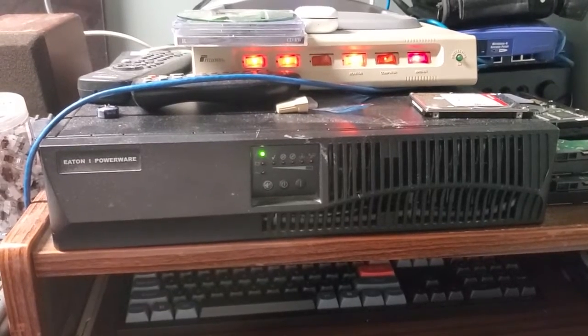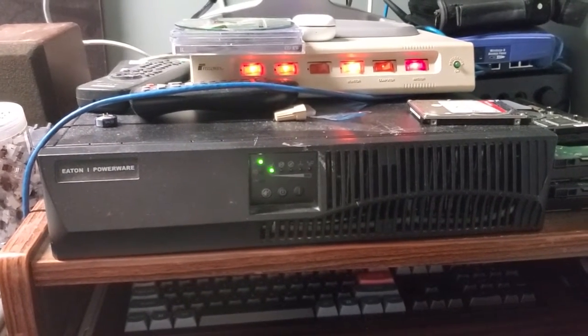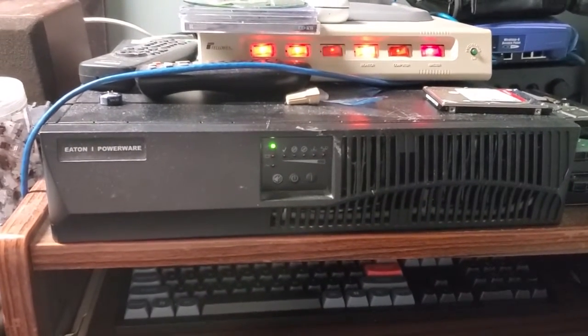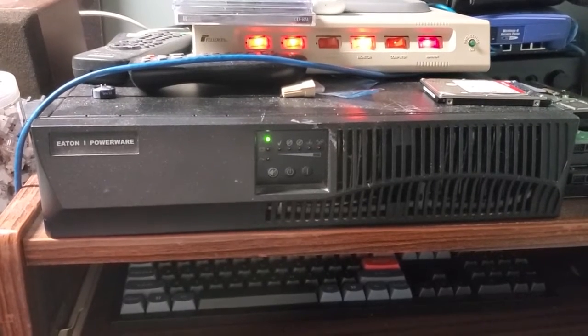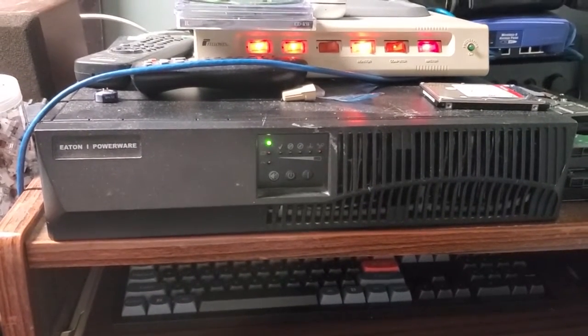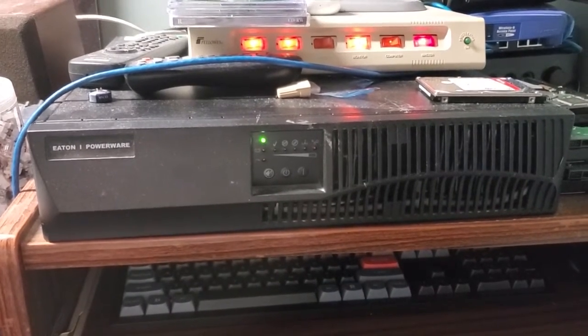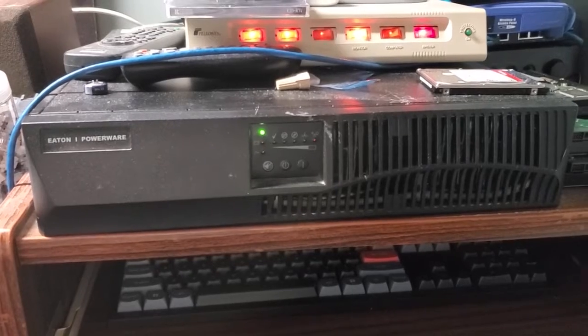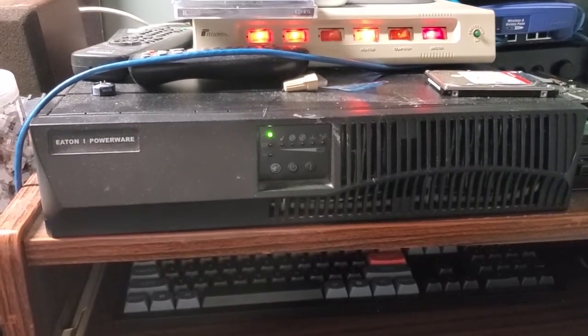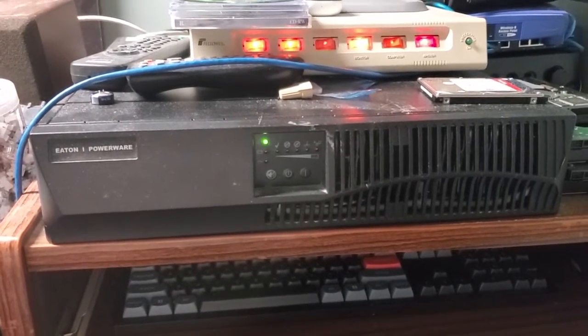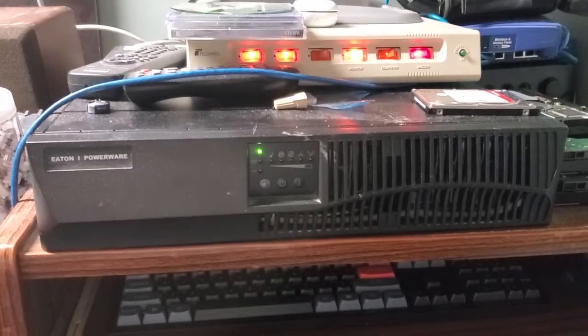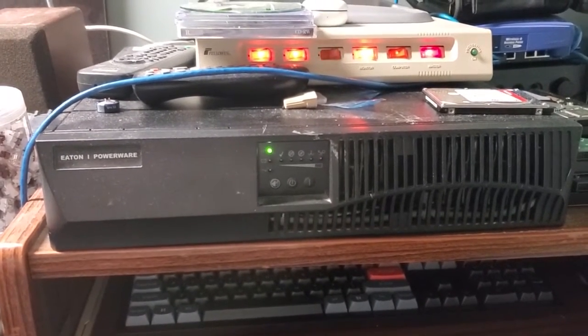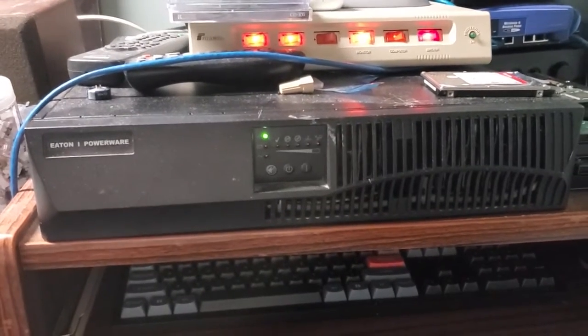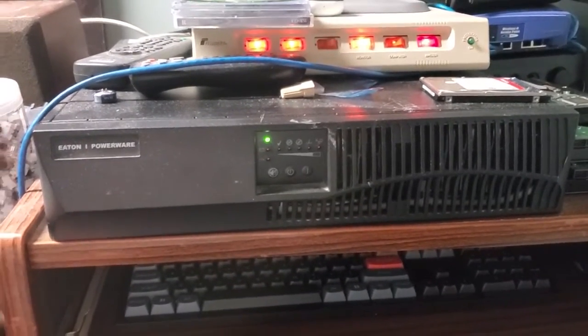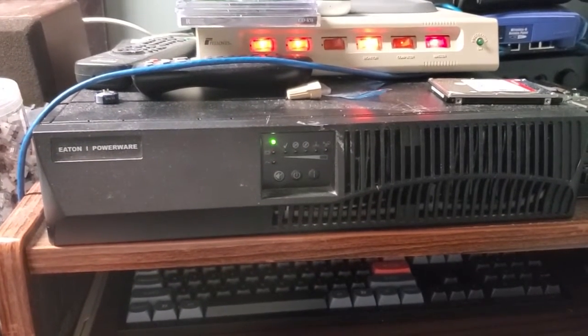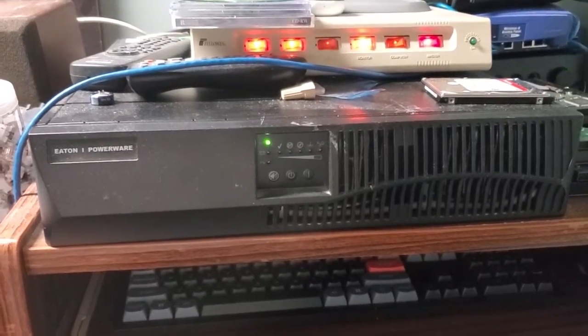And yeah, it's absolutely seamless, extremely sensitive devices will never know that the switch happened. The other benefit is that because power is being supplied from the inverter and not from the mains power, if the mains power is imperfect or a little bit unstable, your equipment will never know, because the UPS is generating its own power all the time that's perfectly stable. The voltage will never vary, the frequency is always perfect, and you are completely protected from the whims of the power company, because the UPS is supplying its own power to the load all the time.